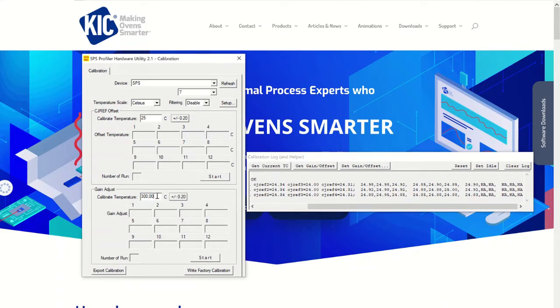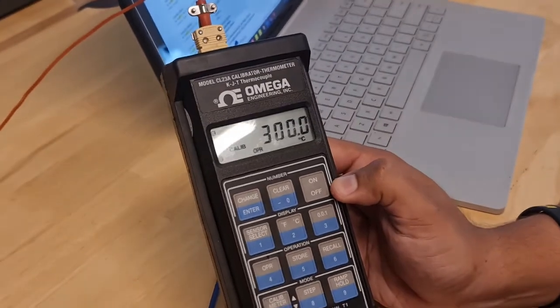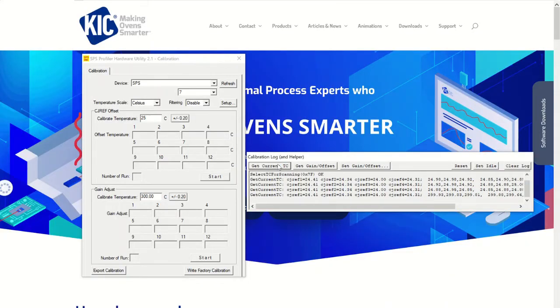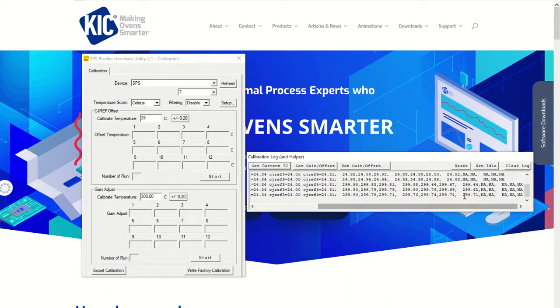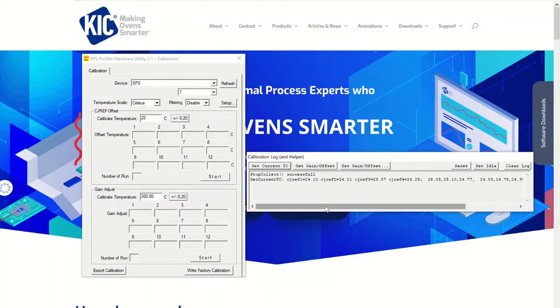Now you must follow the same procedure for the high limit values. Please follow the same steps above, but now set your calibrator simulator to 300 degrees Celsius or 572 degrees Fahrenheit. If both low and high limit temperature readings are within plus or minus 1.2 degrees Celsius or 2 degrees Fahrenheit of the calibrator simulator set point, you do not need to proceed and run the calibration procedure for this profiler. If any of your readings were not within tolerance, please follow the instructions in this next video to calibrate your SPS profiler.